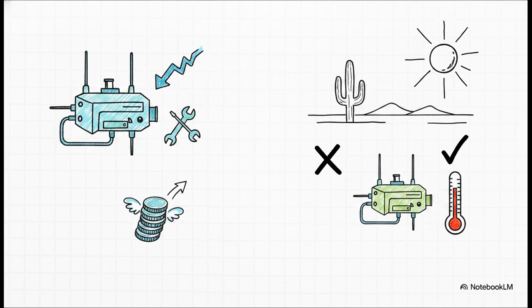The plot twist here is that while enthalpy sounds flawless on paper, it's pretty heavily flawed in practice. Enthalpy sensors are notoriously finicky. They've got high inaccuracy rates of plus or minus 2 BTUs per pound, and even worse, those humidity sensors drift out of calibration really easily over time. That seriously drives up maintenance costs because they need constant recalibration. Also, while it's fantastic in Chicago, this strategy is frankly a massive waste of money in dry places like Albuquerque, where a cheap, simple dry bulb system would do the exact same job without all the added headaches.